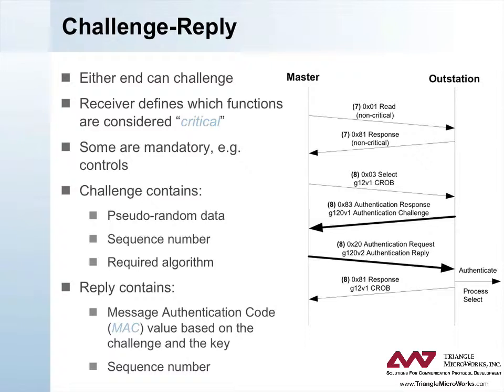If the MAC is valid, the outstation replies with the control relay output block, or CROB, response that the master was originally expecting. Note that DNP3 sequence number rules continue to apply. The entire select sequence uses the same DNP3 sequence number — in this case 8 — including the challenge and the reply. Note also that the select was preceded by a read operation, which the outstation considered to be non-critical, and therefore did not challenge.